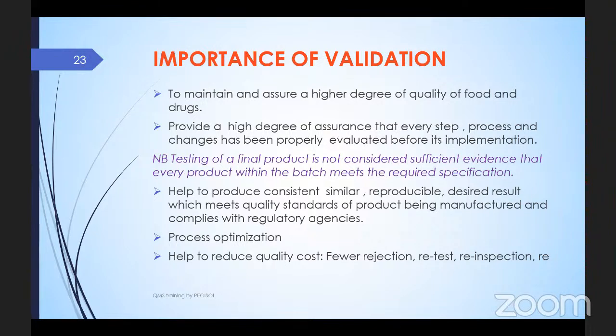Remember, testing the final product is not considered sufficient evidence that every product within the batch meets the required specification. So you have to validate. To help produce consistency, reproducibility, and the desired result, which meets the quality standard of a product or a service. To help with process optimization, to help reduce the cost of quality, fewer rejections, fewer retesting and inspection. All these are important for what? Validation.